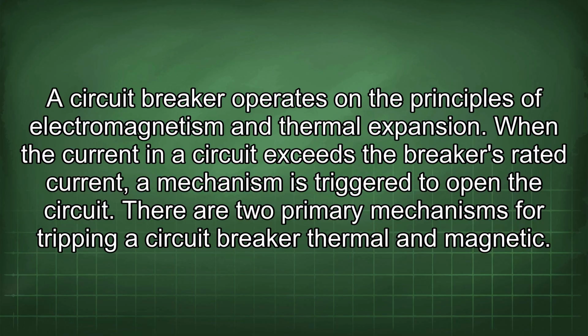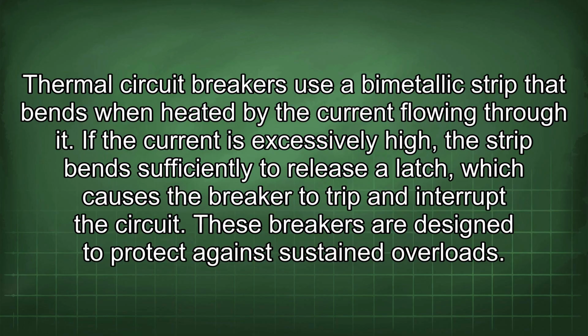There are two primary mechanisms for tripping a circuit breaker: thermal and magnetic. Thermal circuit breakers use a bimetallic strip that bends when heated by the current flowing through it. If the current is excessively high, the strip bends sufficiently to release a latch, which causes the breaker to trip and interrupt the circuit. These breakers are designed to protect against sustained overloads.